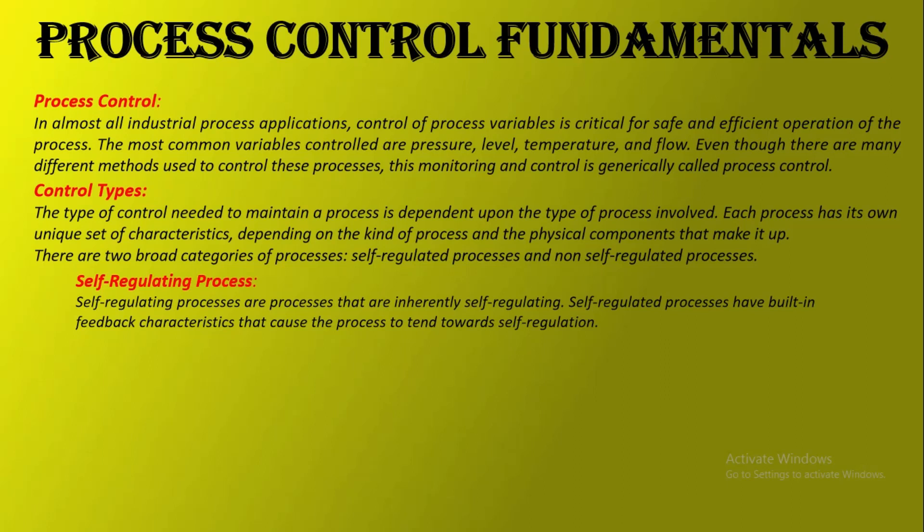What happens if the outlet is opened one-eighth of a turn and water leaving the tank changes to a rate of 25 gallons per minute? Since this is a self-regulating process, the level will stabilize at a new position. Flow out of the tank is proportional to the square root of the differential pressure across the outlet valve. As level decreases, the differential pressure also decreases, causing the drainage rate to decrease until it equals the fill rate and the tank reaches a new equilibrium point.